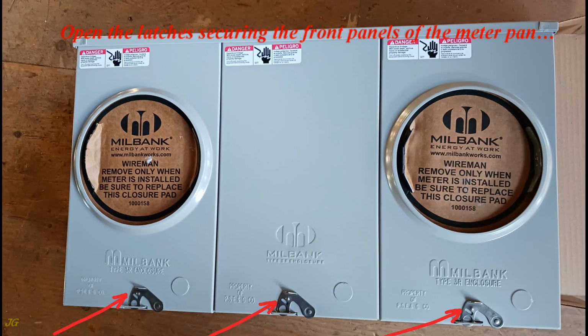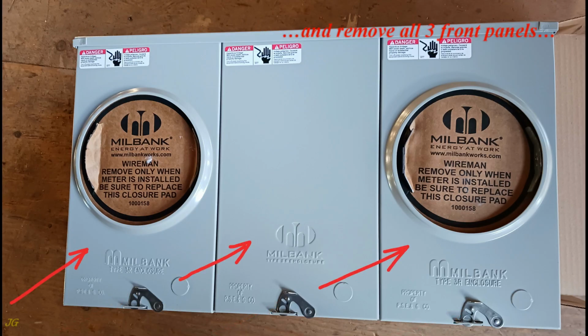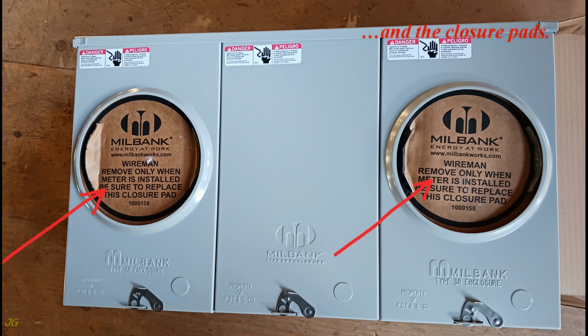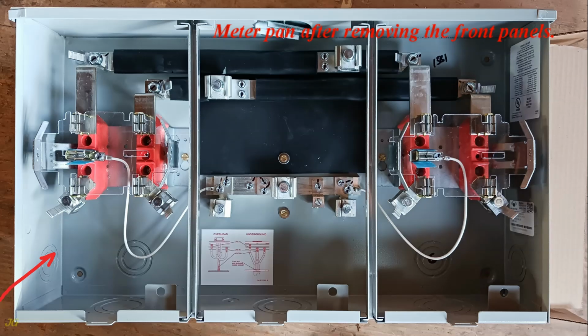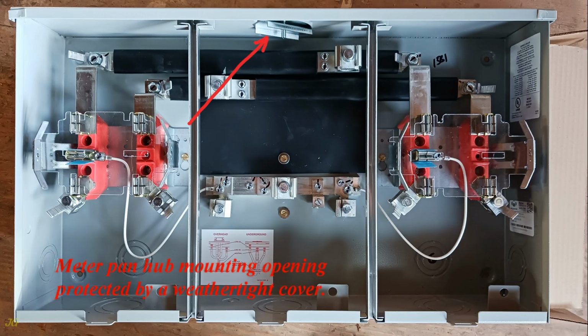Open the latches securing the front panels of the meter pan, and remove all 3 front panels and the closure pads. Meter pan after removing the front panels. Meter pan hub mounting opening protected by a weathertight cover.